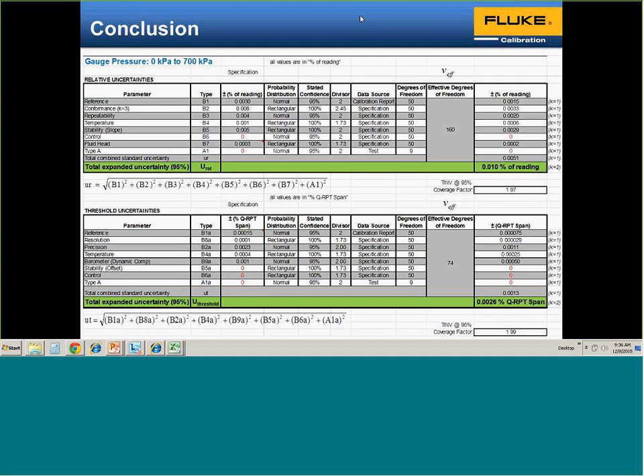This particular example is for a 700 kPa QRPT. Do you have an uncertainty analysis for other ranges of QRPT for QBTs? Yes, there's a guide on a website called Guide to Determining Pressure Measurement Uncertainty for QRPT-based products. It's available and goes into much more detail on the QRPT. There's also a paper available on the uncertainty of the quartz tube as mentioned in the user manual for that product.